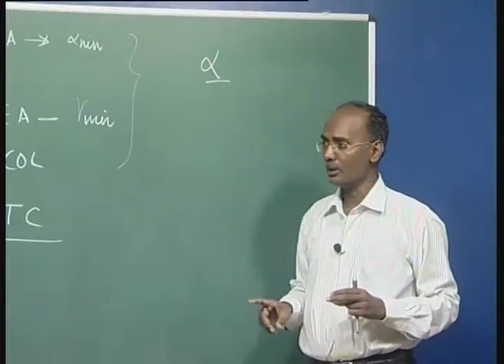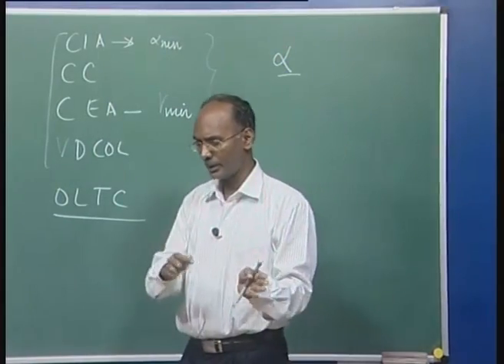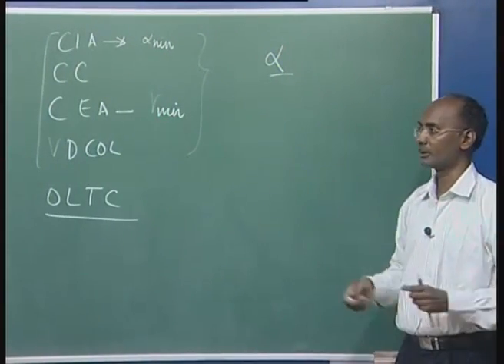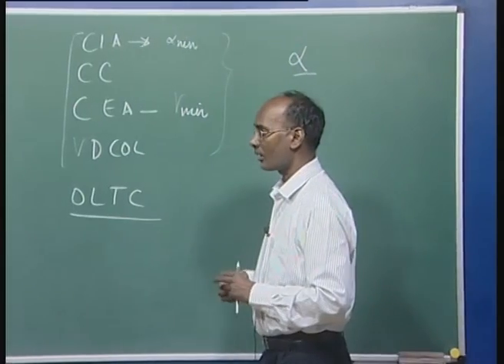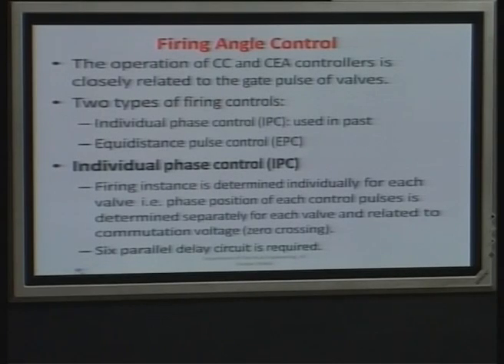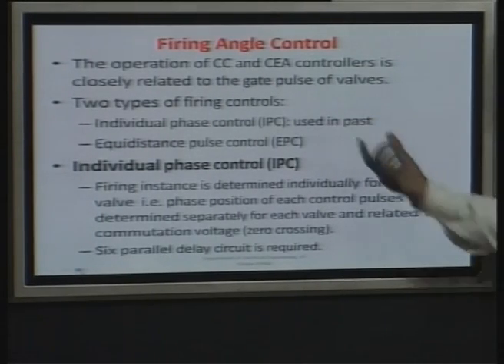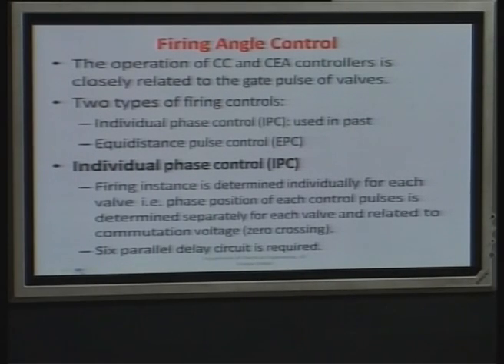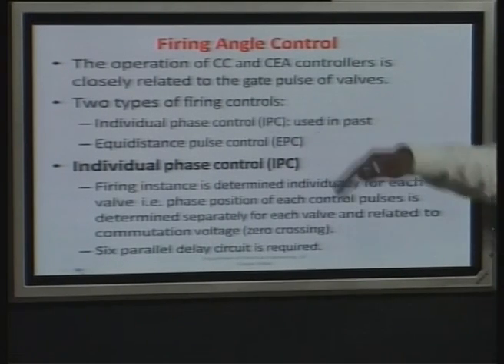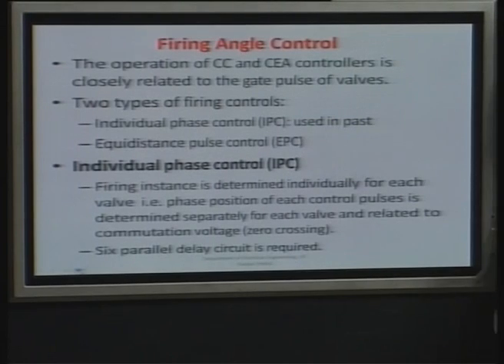In the literature, there is firing angle control. The firing angle — whether it is a rectifier or inverter — we have to have this alpha. If alpha is less than 90 degrees, then it is rectifier mode; more than that, it is inverter. There are two schemes popularly used: individual phase control (IPC), which was used in the early days with mercury arc valves, and equidistant pulse control (EPC), which most modern HVDC control stations use. We will discuss both the IPC and EPC differences, advantages, and disadvantages.